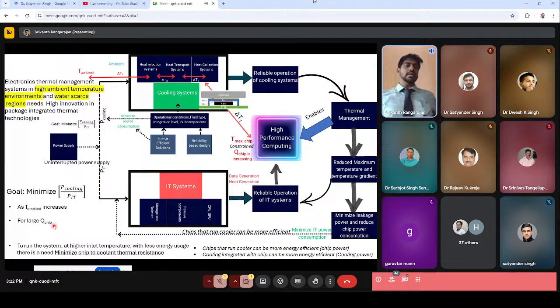So to run the system at higher inlet temperature with less energy usage, there is a need to minimize the chip to coolant thermal resistance, which means the chip that can run cooler can be more energy efficient because it draws very little chip power, since the leakage power consumed by the chip is a direct function of the chip's temperature, and the cooling integrated with the chip can be more and more energy efficient.